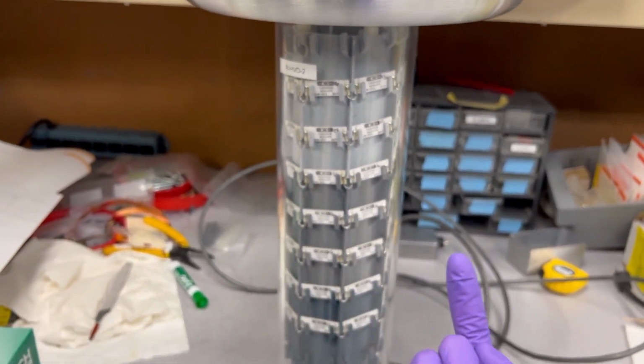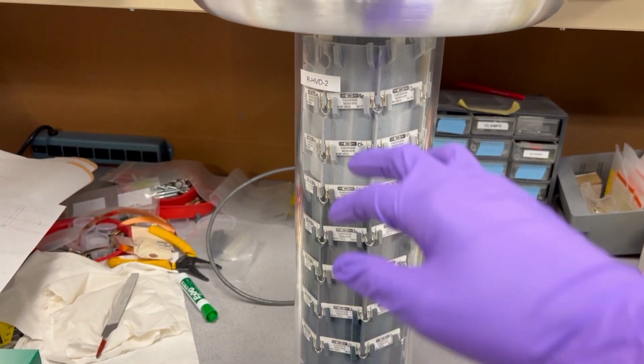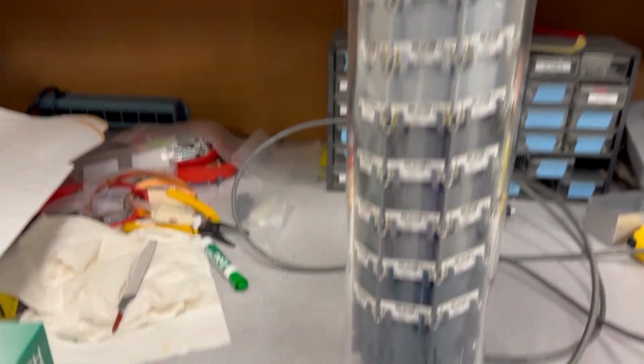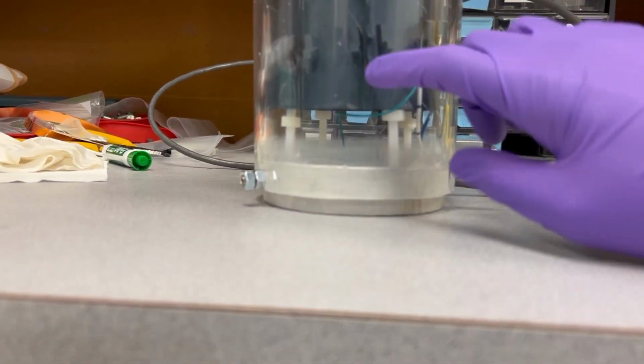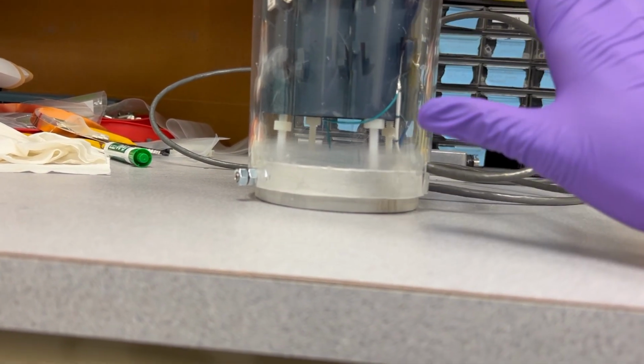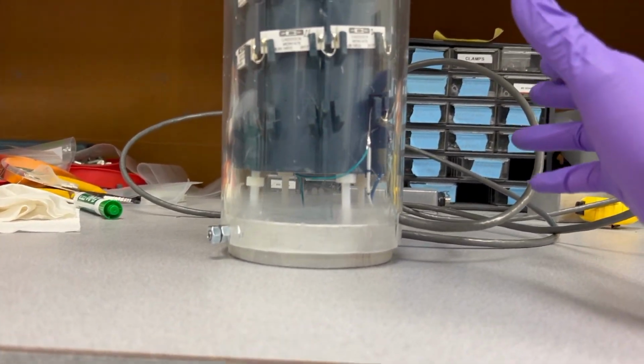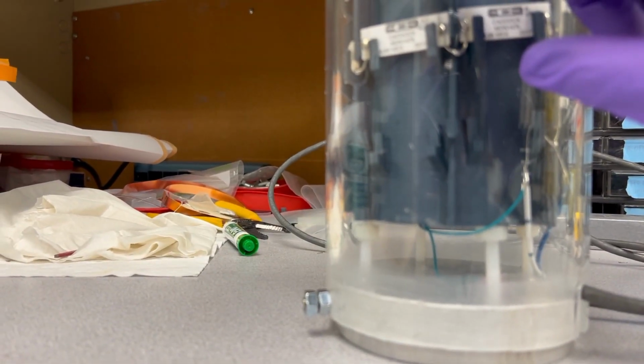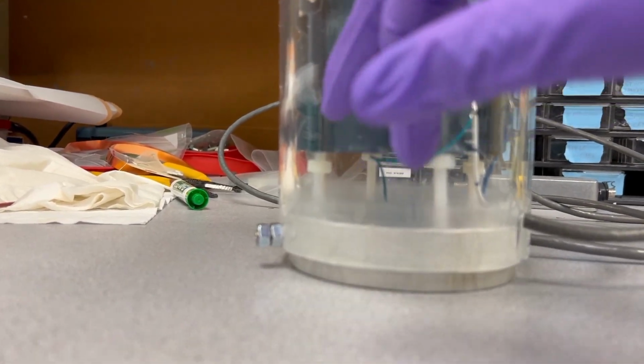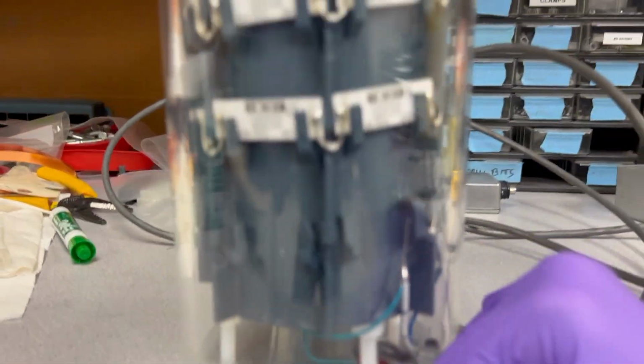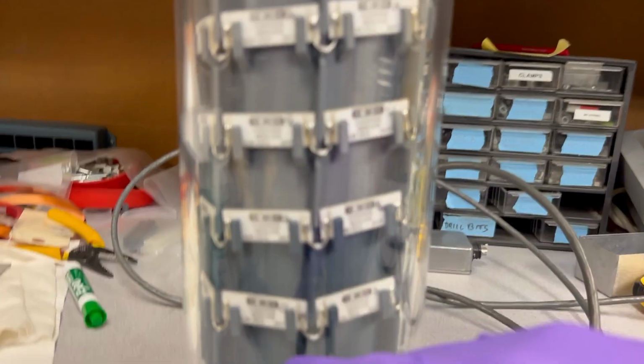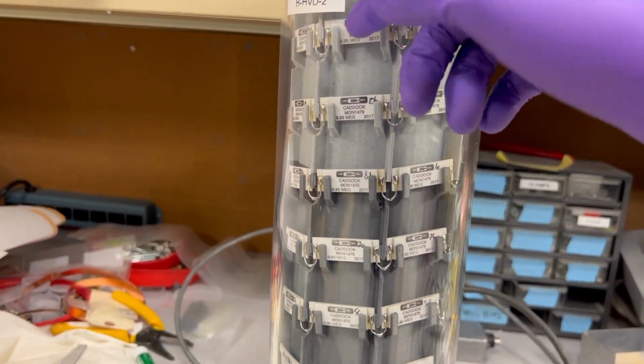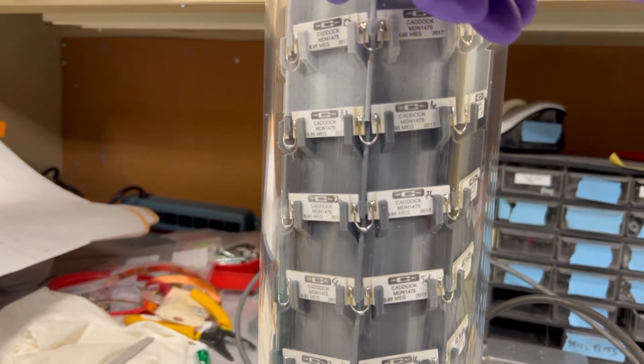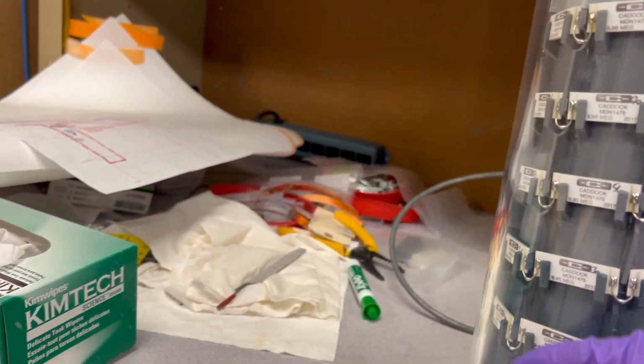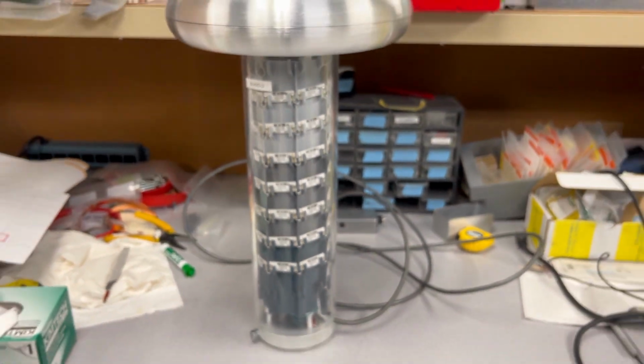Looking at the body, we see the acrylic tube that protects the resistors that are aligned in a helix spiral all the way down the body and rest on the 3D printed part. Down here we have the aluminum support. This version does not have the heatsink and the fan because it was not needed for its application, but the one running at Becla has that, and we can see there's a gap between the support and the 3D printed structure to allow for airflow. When the fan is here, the fan blows air up along the body of the tube, and it will come through here all over the resistors and then back down and circulate to cool the whole system.